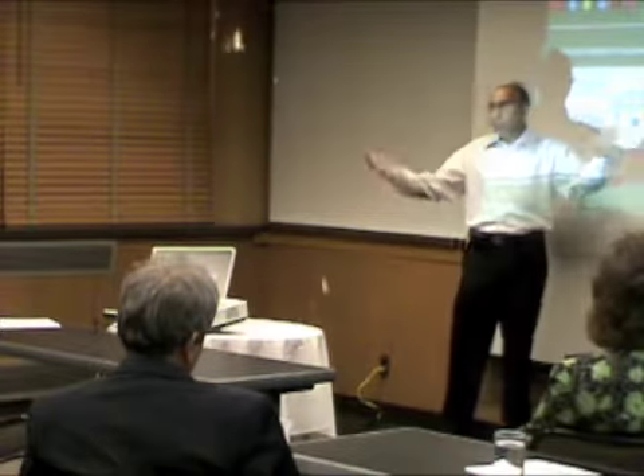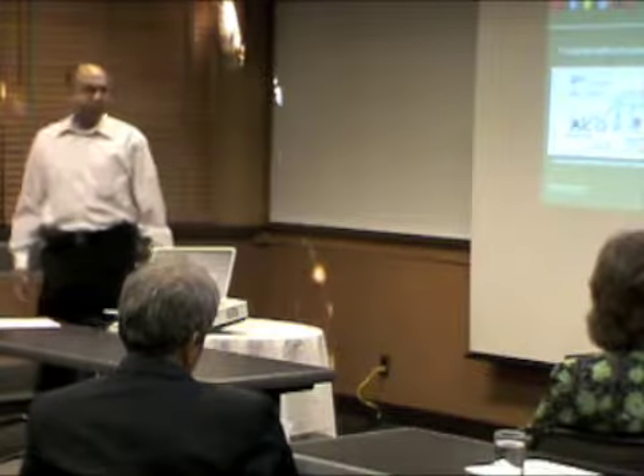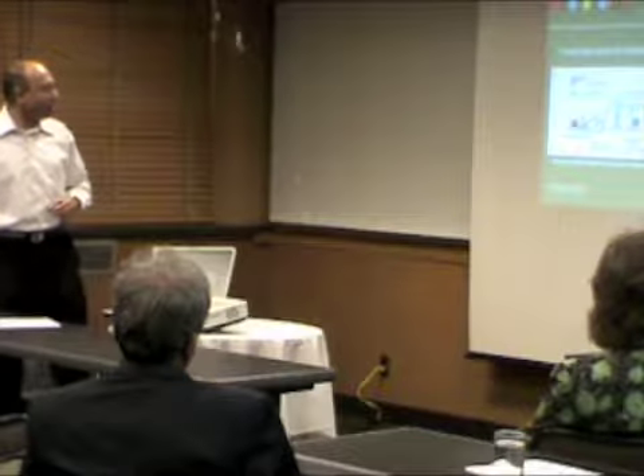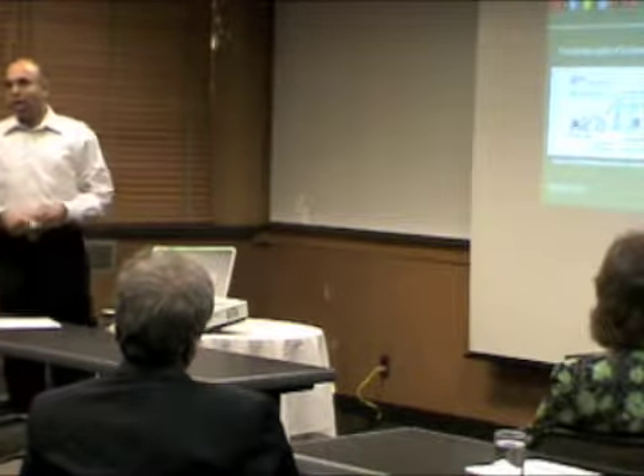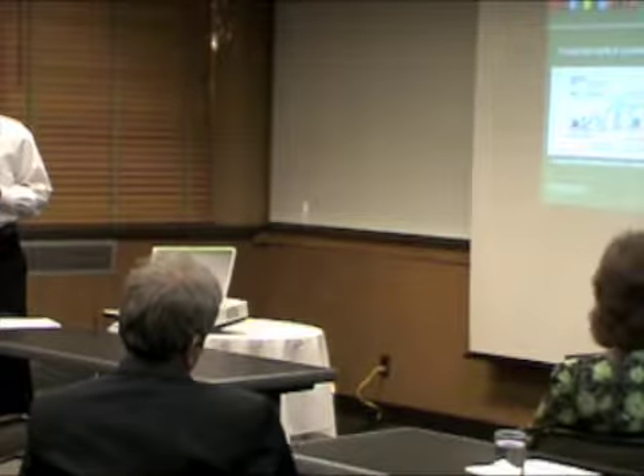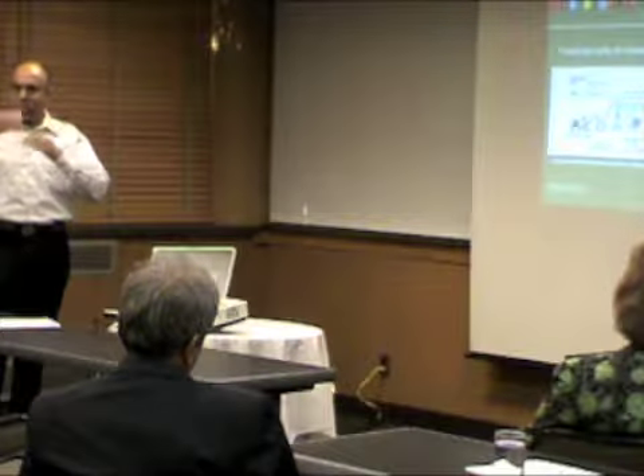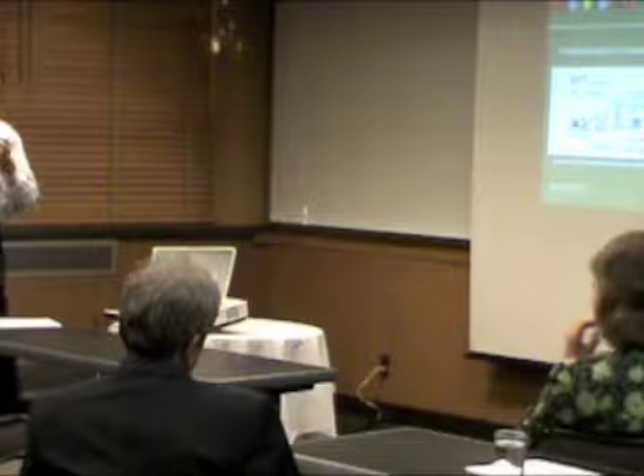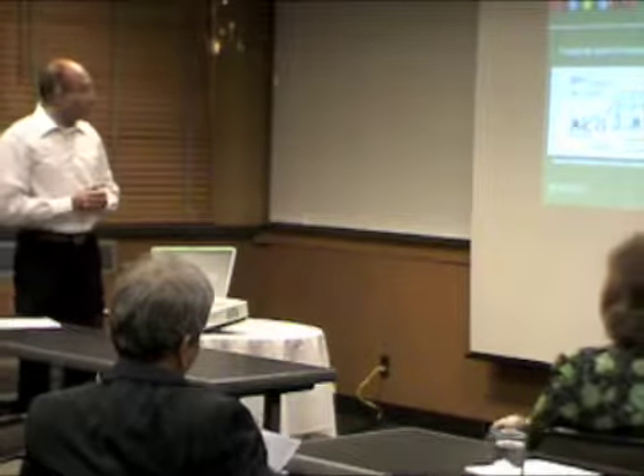Primary, in the distribution system, the term primary is used to denote customers that take three-phase power. And then we have secondary customers, like us, residential customers. Secondary is used to denote single-phase power. So the stuff you get out of the wall socket is secondary. So what happens is single-phase power is sent out to you at between 4,000 to 7,200 volts. There's a pole-top transformer that steps it down to 120 and 240 volts. So it's like there's a center tap at 0, then there's a 120, and there's another 120 on the other side, displaced 180 degrees in phase. So across the two outer terminals, you get 240 volts, which you use to drive air conditioners, electric dryers and things like that, cooktop. Everything else gets 120 volts. So that's what comes out of the wall socket.